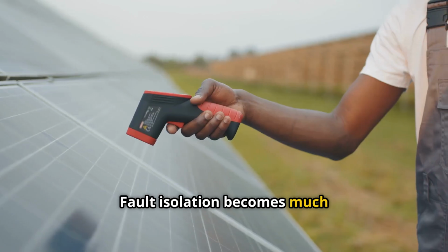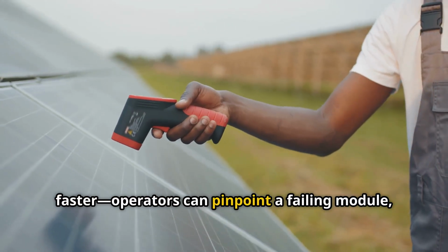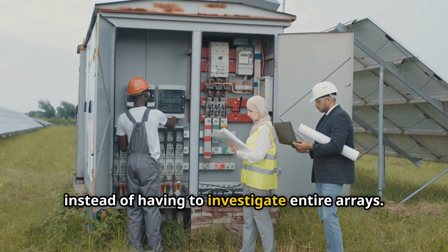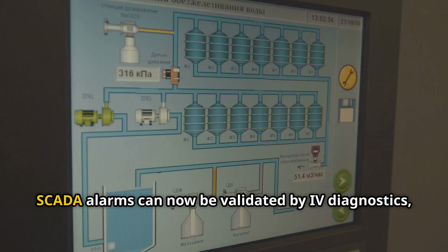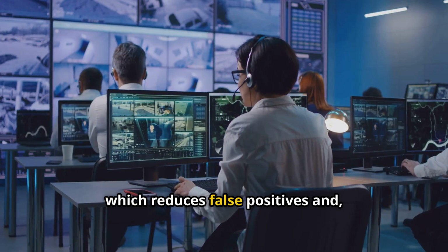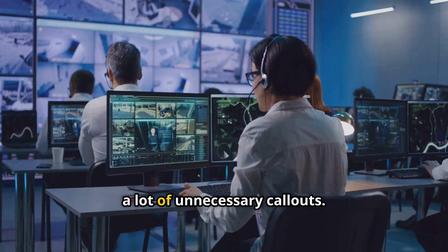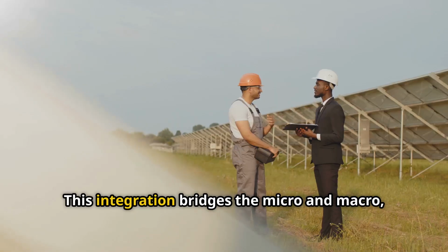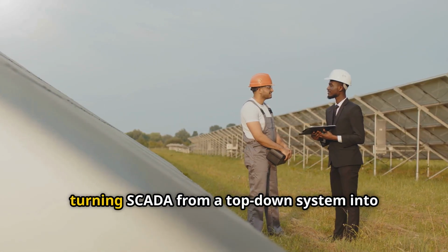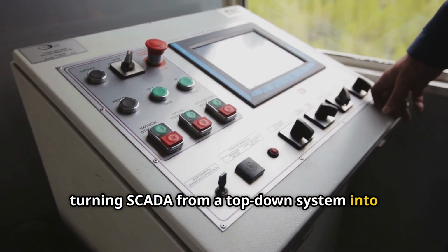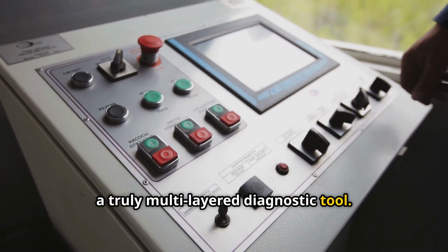Fault isolation becomes much faster. Operators can pinpoint a failing module, instead of having to investigate entire arrays. SCADA alarms can now be validated by IV diagnostics, which reduces false positives and, honestly, a lot of unnecessary callouts. This integration bridges the micro and macro, turning SCADA from a top-down system into a truly multi-layered diagnostic tool.